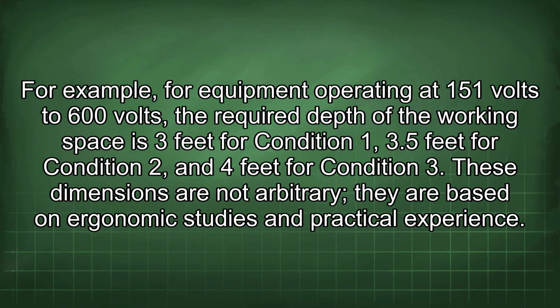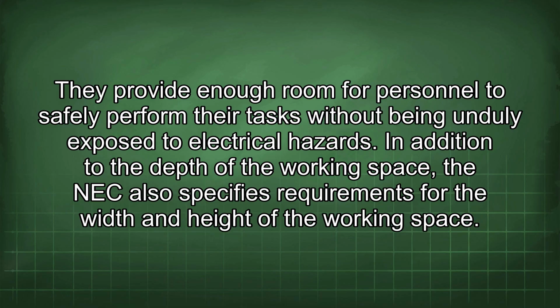For example, for equipment operating at 151 volts to 600 volts, the required depth of the working space is 3 feet for condition 1, 3.5 feet for condition 2, and 4 feet for condition 3. These dimensions are not arbitrary, they are based on ergonomic studies and practical experience. It provides enough room for personnel to safely perform their tasks without being unduly exposed to electrical hazards.